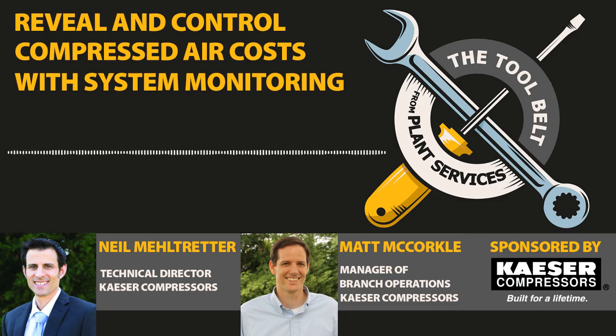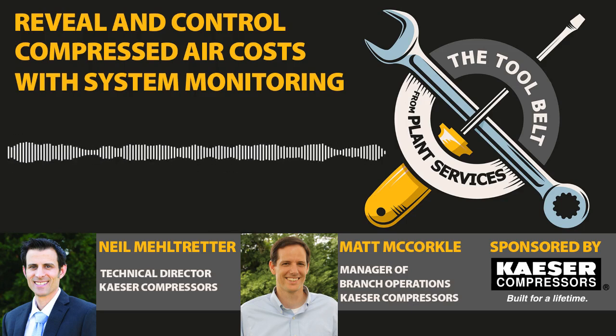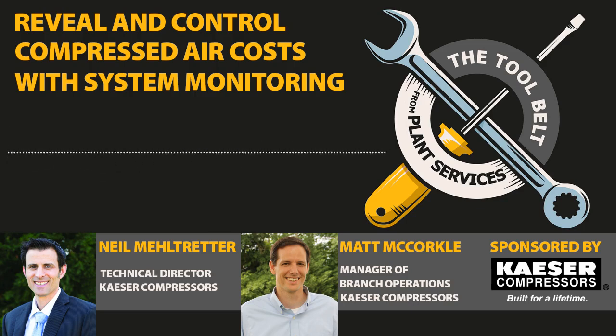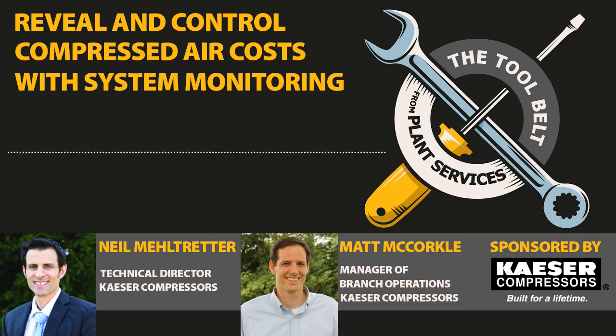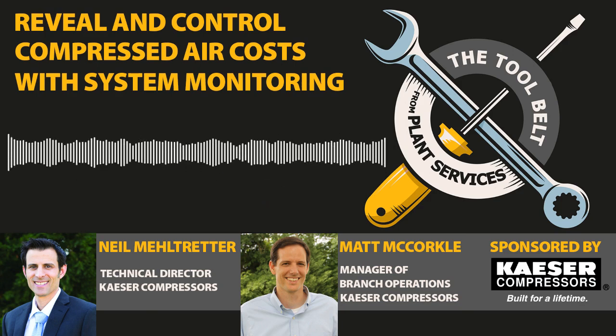And the kind of push data or technology that's out there, you have Ethernet IP, you have Modbus TCP, there's BACnet here in the US or Profinet worldwide. We're seeing a lot of call now for OPC UA as well. So those are some of the protocols that you'll see customers request depending on what kind of control system they're using today. And whether it's an additional module you might need, or a converter box, or it's automatically included, or you have to get a release code, there are a lot of different options depending on manufacturers.